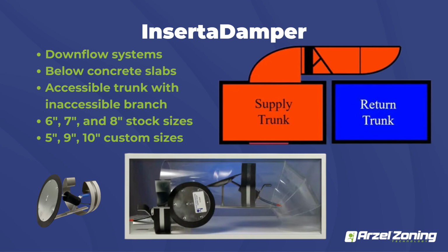But as far as the InsertaDamper, which is the first one we'll cover here, works really well if you guys got a slab home. So if they have a slab that isn't metallic ductwork, you can use this specific damper. It has a metal band on the damper itself. You can see in the picture in the clear tubing. You would squeeze that band and stick that into your ductwork. Once you let it go, it opens back up from the spring. That's going to hold that damper in place.